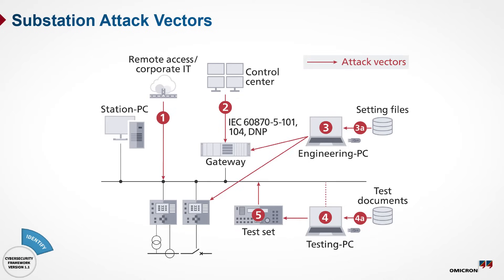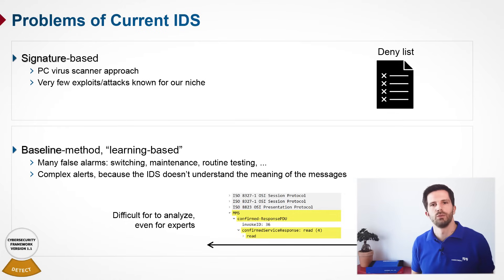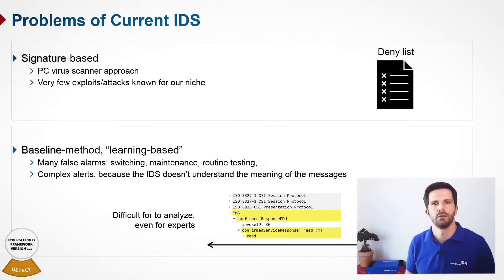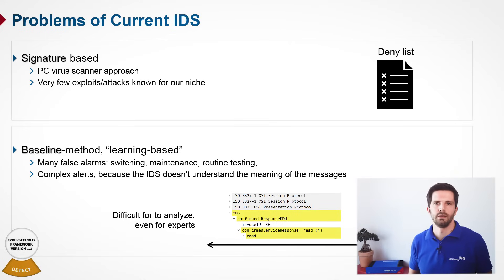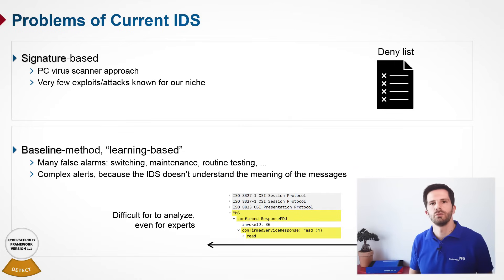When applying intrusion detection in a substation or generally in OT systems, there are mainly two approaches available, both with certain drawbacks. The first and oldest approach is the signature-based approach, the same as with a virus scanner. The problem is it can only detect attacks which are known and have an entry in the deny list, so only known threats can be detected. For power systems, this is clearly not a good approach.